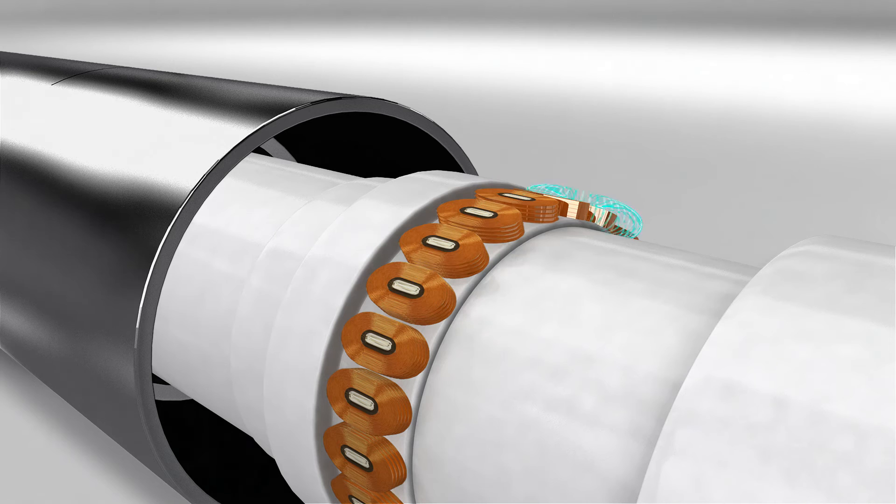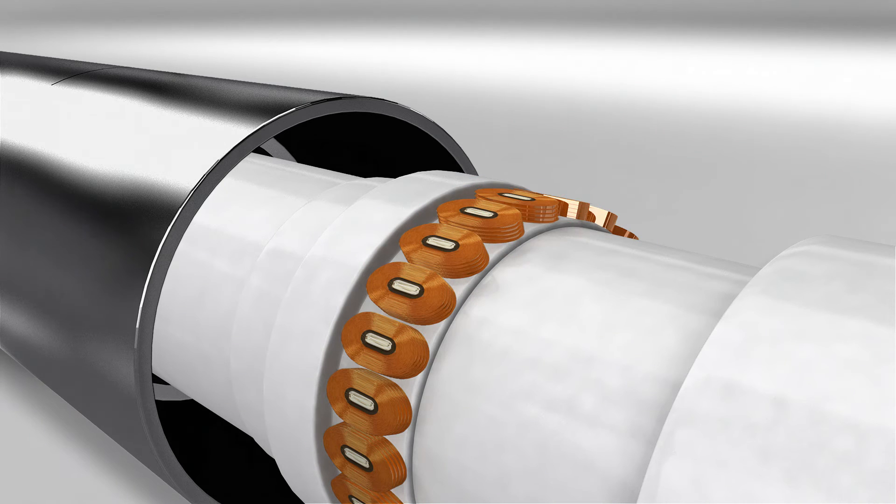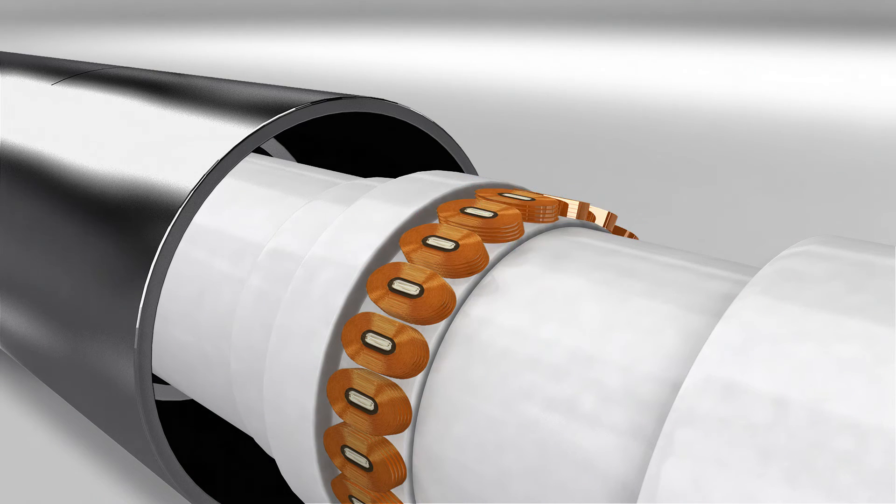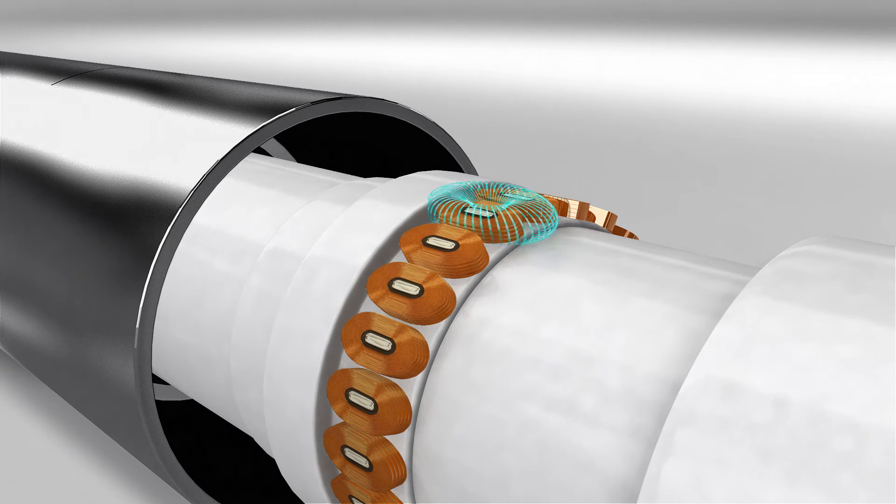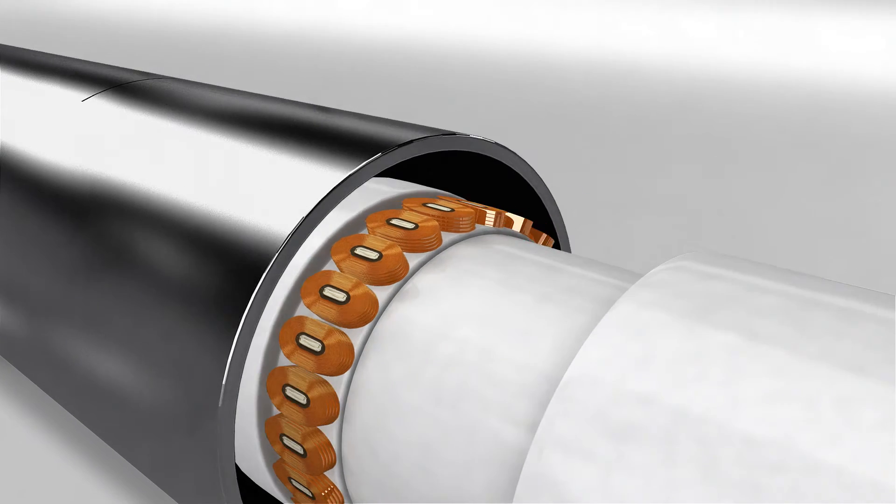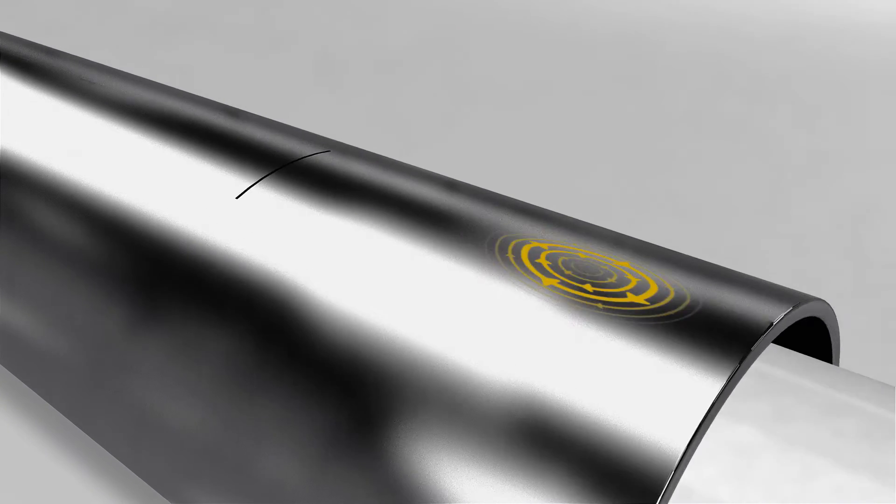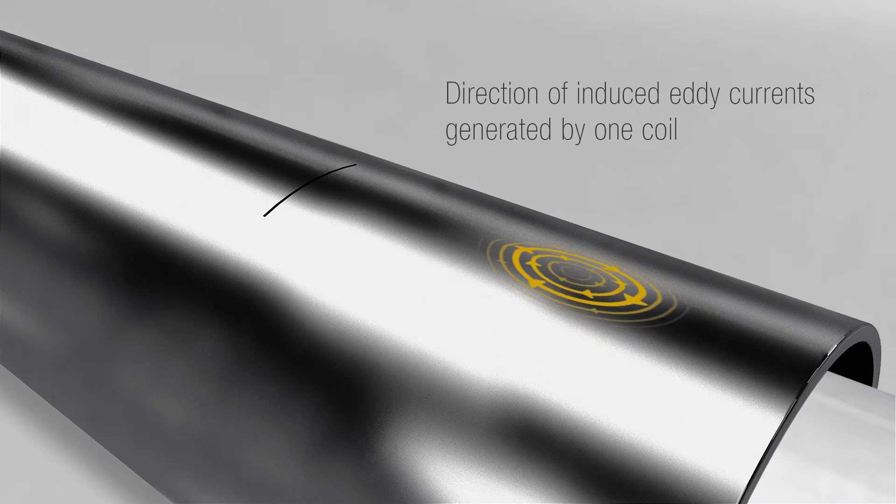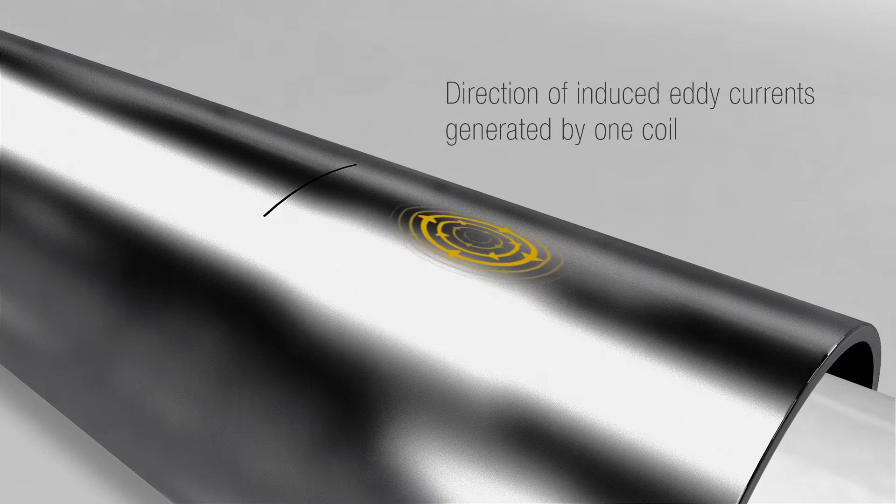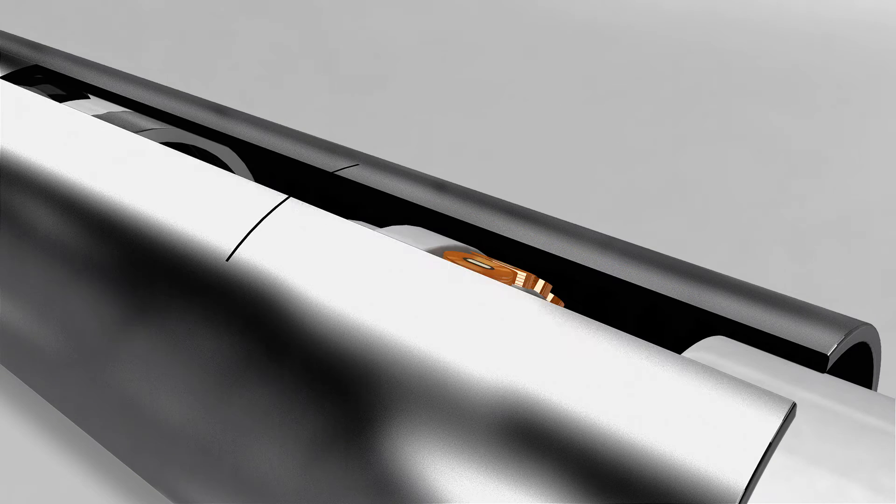Multiplexing is key here. The coils are driven sequentially in a clever pattern. This enables the Eddyfi probe to examine the entire circumference of the tube with no mutual interference between the coils. The result? High definition data.